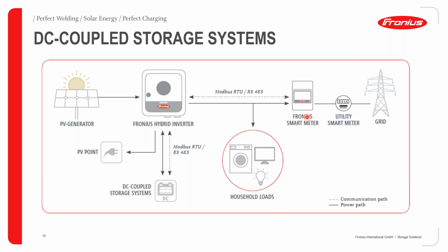Okay, we also have the Fronius smart meter, which has to be installed in a DC coupled storage solution with Fronius. Okay, so this is compulsory, and this will communicate with our hybrid inverter over Modbus RTU. Okay, you will then also have the utility prepaid meter before the grid as well. Okay, in between the Fronius hybrid inverter and the Fronius smart meter, you'll then have your AC loads. Our Fronius hybrid inverter can then communicate over Modbus RTU with the battery storage. And as I alluded to earlier on, we can also offer the PV points as well on the inverter.